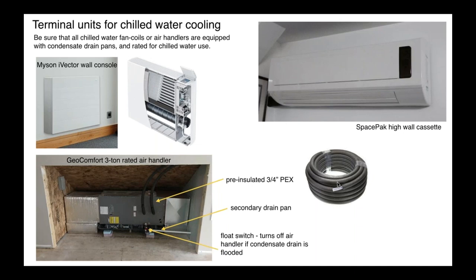We could route this up from the basement mechanical room to the second floor where this air handler is very easily relative to putting sticks of copper in and trying to slide all that insulation. I can't overstress how important it is to do a good job with that insulation. If you're new to chill water cooling, you can't get sloppy with the insulation. The joints have to be glued. The seams have to stay together.